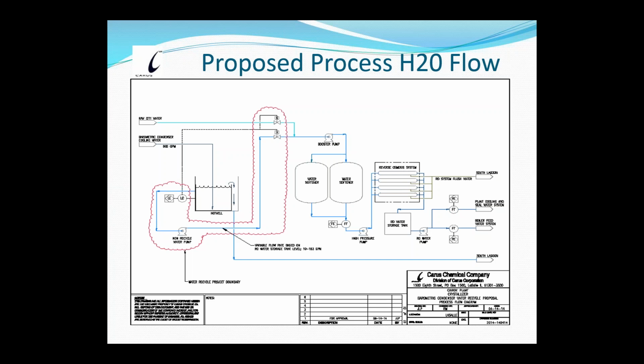Here is the hot well that I was speaking about. What's in blue, or in the red wavy line, is the new process, the new lines that I put in to allow us to feed spent cooling water to the softeners instead of using raw city water. You can see there's the pump right here. We have the conductivity probe and a level controller. And then we have two automatic valves right here. That then pumps into the booster pump that then goes into the water softeners.